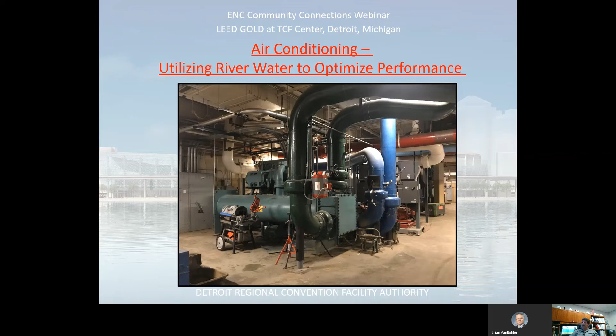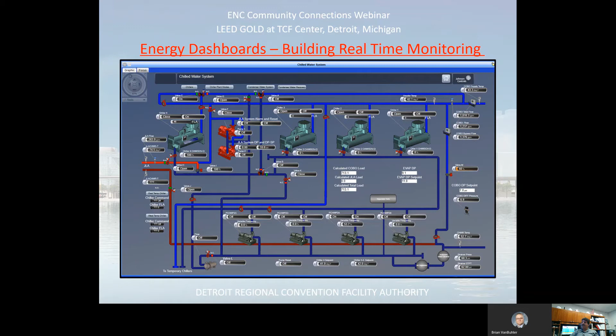If things are off, we're not sending water to that area, and I save on horsepower and again increase efficiencies. We watch the entire system with our building automation system to know the loads - not only how many chillers I have on, but what the loads are, what's approaching, and what are the best machines to use at any one set point in time.